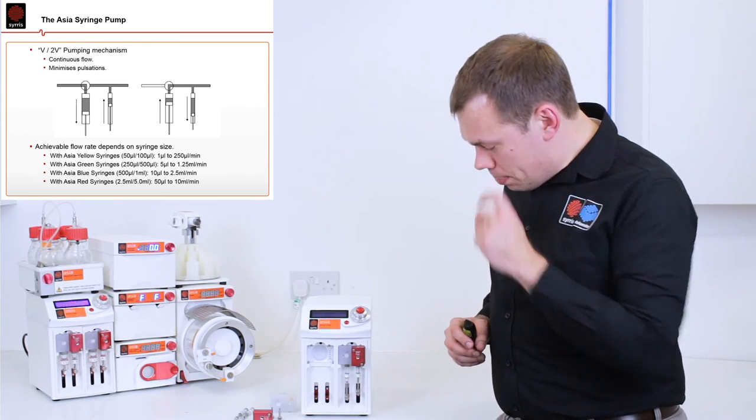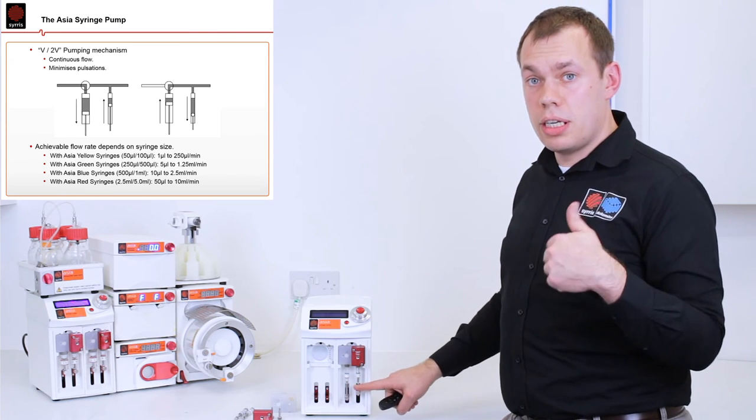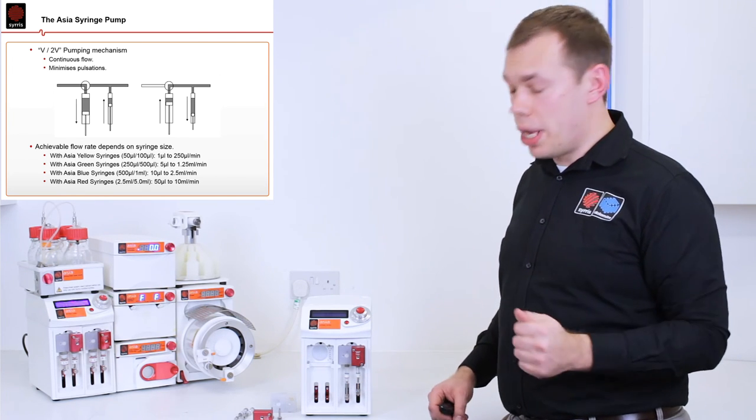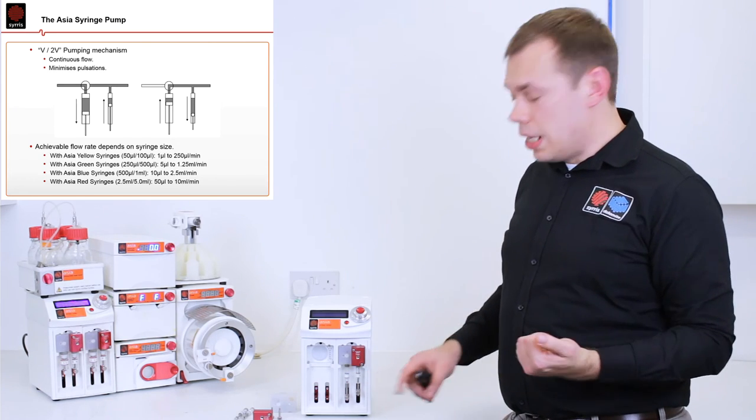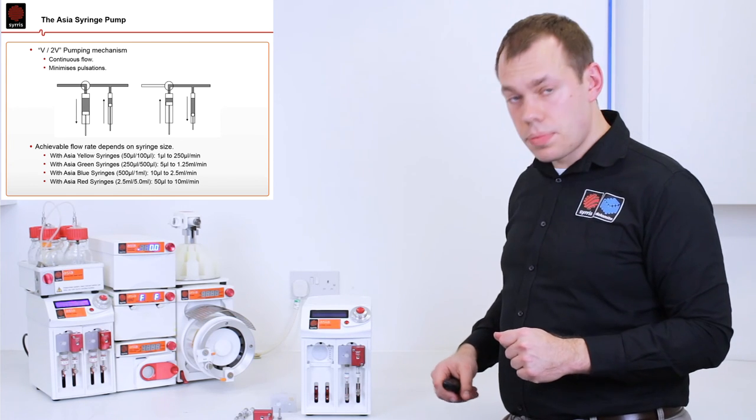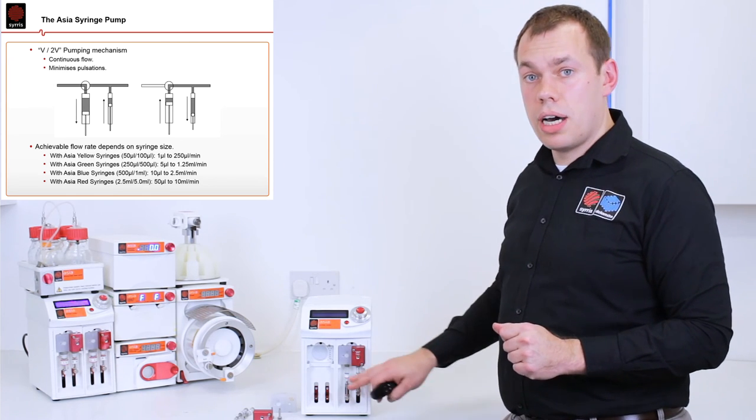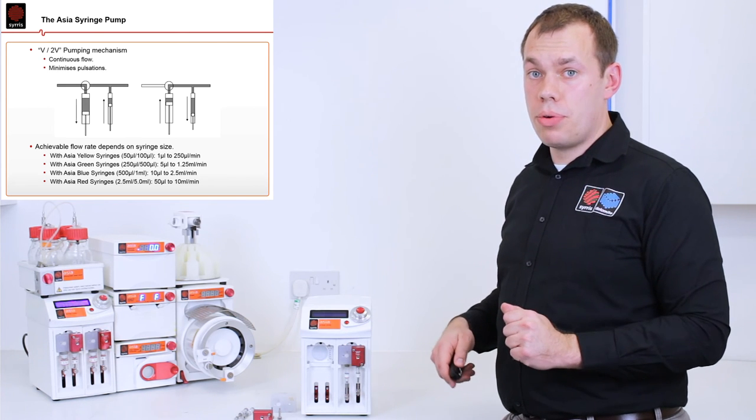The pumping mechanism is called V2V and uses two syringes that enable the continuous flow of solvents or reagents. When one of the syringes is pulling to refill, the other one is dispensing the volume out into the system. All the wetted parts are glass and PTFE enabling maximum chemical resistance.